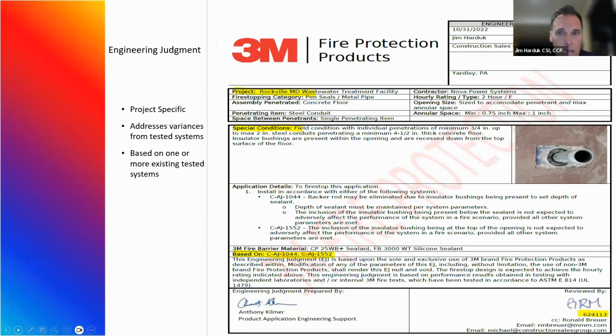So you'll notice that our engineering judgments are laid out very similar to what the UL system drawing would look like. Then there are a couple key components that we have to capture every time we submit a request for an engineering judgment. These are project specific, so we always need to know what the project name is and the location. And then, of course, we have to identify whatever the special conditions are. So basically, any variances from the tested system will be listed here. And then following that will be the application details. It'll tell you how to address those conditions.